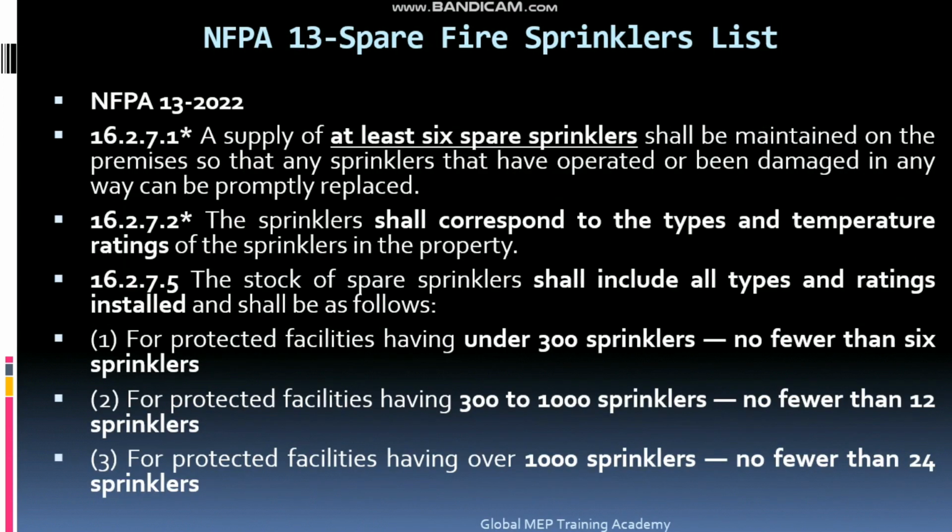And we need to have spares for all types of sprinklers used in the building. Like if we have pendant, upright, ESFR, CMSA, then we need to have stock for all the sprinklers. Also, we need to consider the temperature rating, K factor, etc.